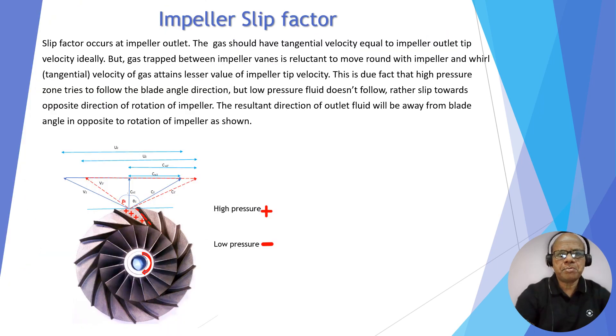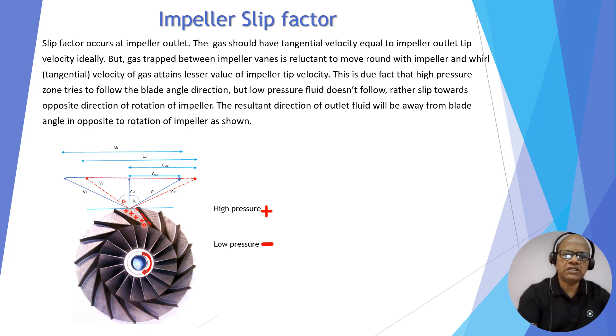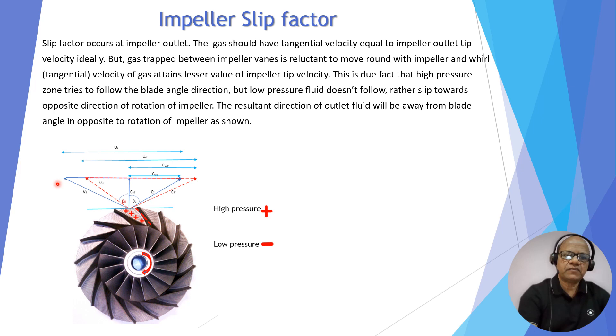Let's begin the discussion on slip factor. First of all, let us understand what slip is. Slip occurs at the impeller outlet, as shown here. The gas has to follow the tangential component along the blade angle, but it doesn't — it slightly goes backward. This is because when the impeller is rotating, there is a high pressure side and a low pressure side. The high pressure side follows the blade angle, but the low pressure side doesn't — it slightly diverts. So overall, the actual velocity comes out slightly in the backward direction, opposite to the direction of rotation, and this is called slip.